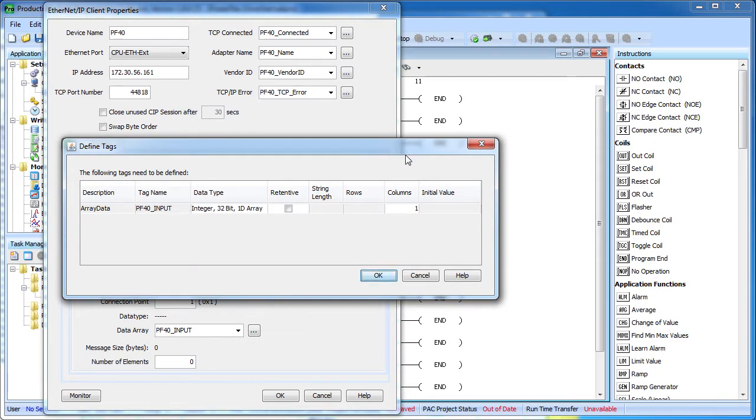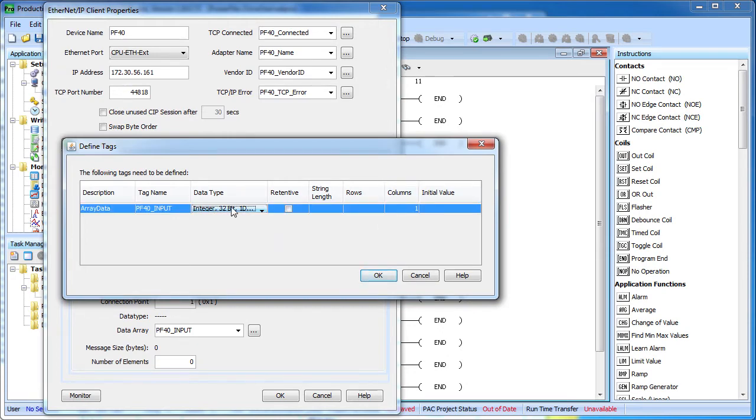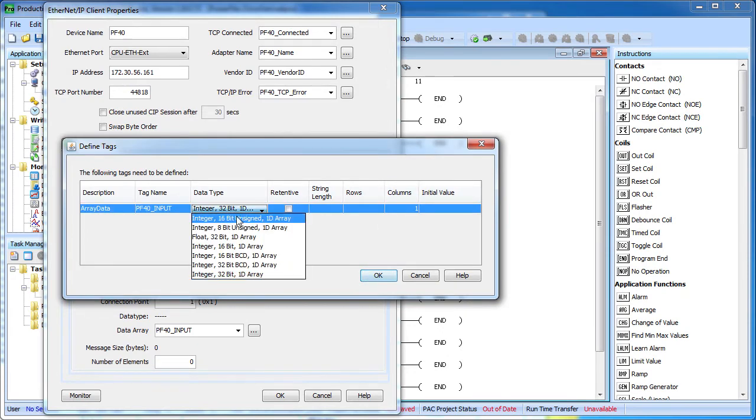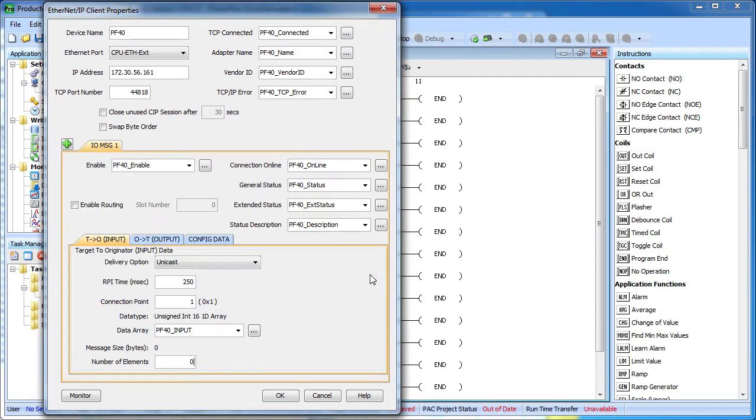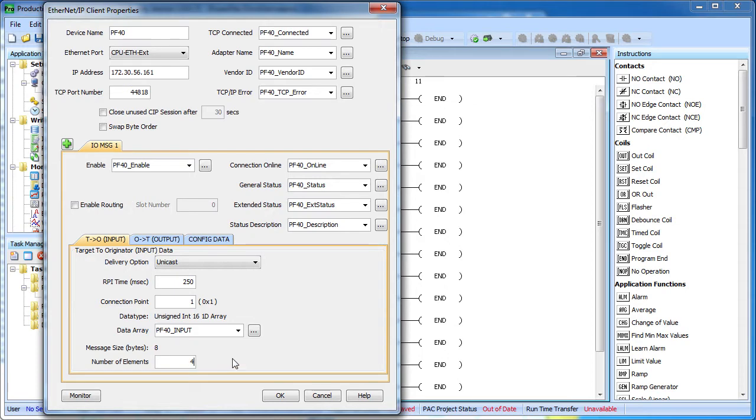The software reminds us that we haven't actually created that tag yet and it gives us an opportunity to do so. I really love that I don't have to create my tags ahead of time. I can just create them on the fly as I go. According to the documentation we need for these to be 16-bit unsigned integers and depending upon the setup you have, you may need up to 12 of these. So let's go ahead and plan ahead for that and say OK. How many of those elements you use depends on what kind of multi-drive setup you have. We're only using a single drive and according to the documentation we only need 4 of those elements to do that setup.